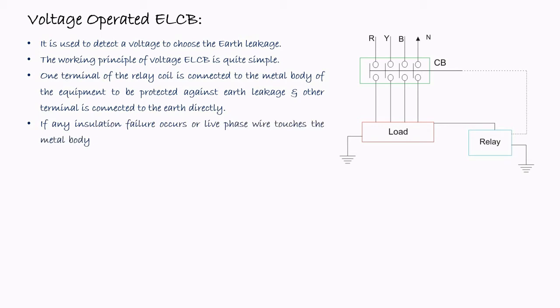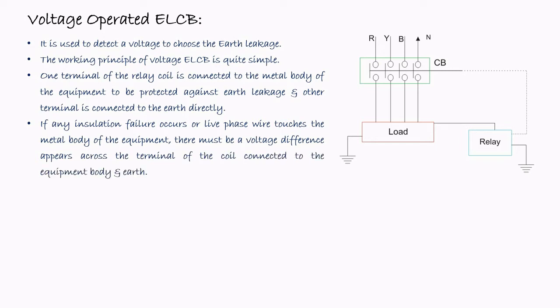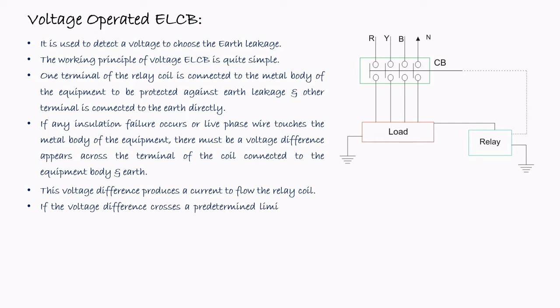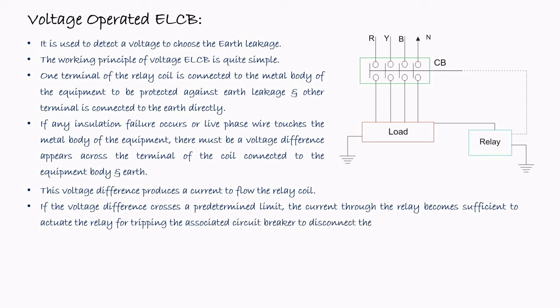If any insulation failure occurs or a live phase wire touches the metal body of the equipment, a voltage difference appears across the terminals of the coil connected to the equipment body and the earth. So there will be a voltage difference, and this voltage difference produces a current to flow through the relay coil. Now, if the voltage difference crosses a predetermined limit, then the current through the relay becomes sufficient to actuate the relay for tripping the associated circuit breaker to disconnect the power supply to the equipment.